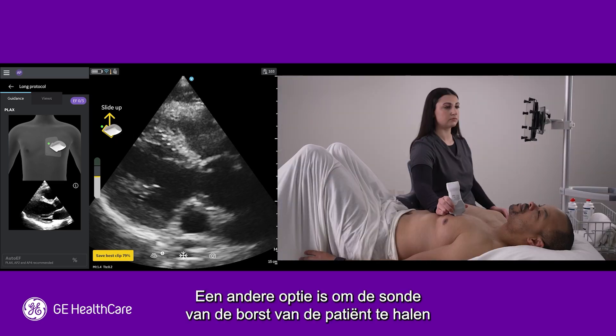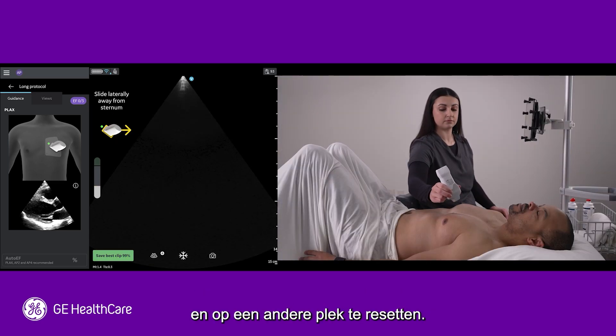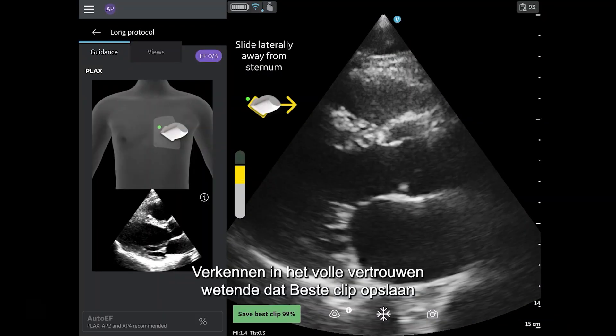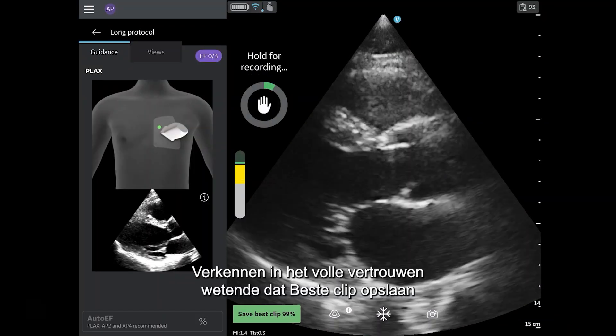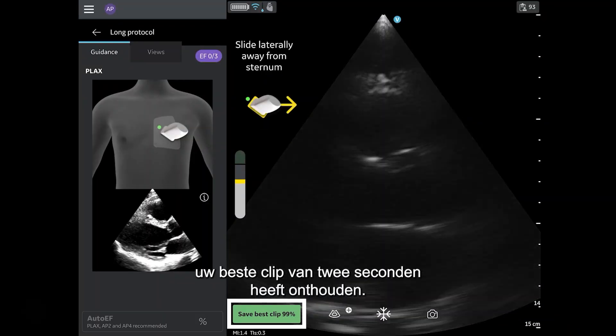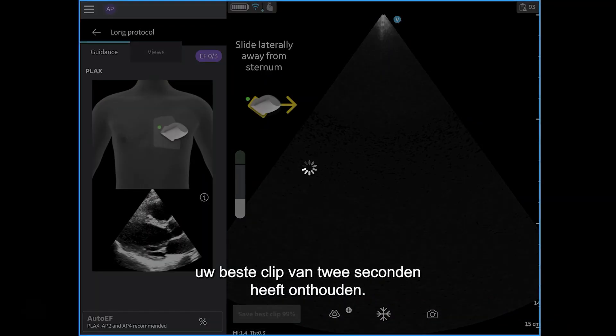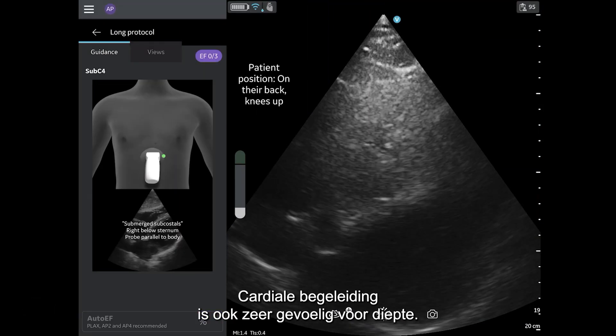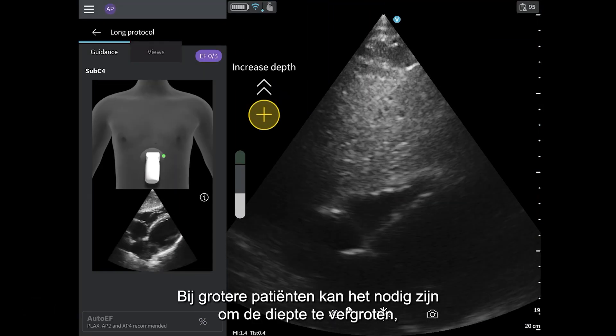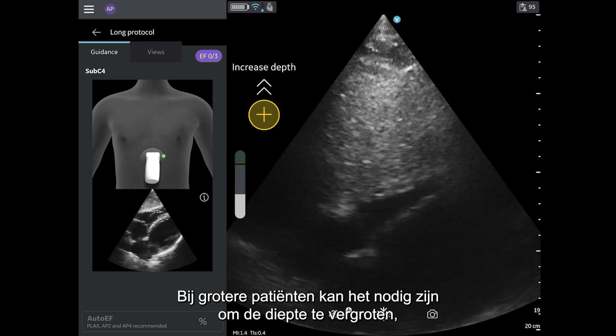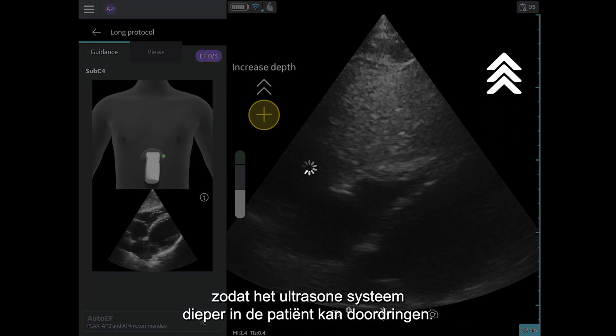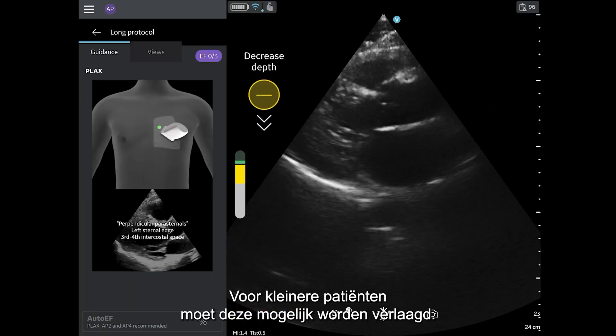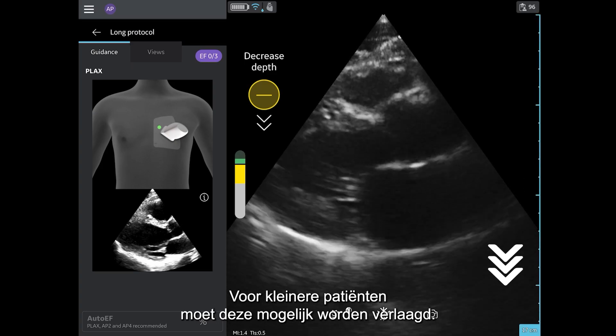Another option is to take the probe off the patient's chest and reset in a different spot. You can explore with confidence knowing that Save Best Clip has remembered your best two-second clip. Cardiac guidance is also very sensitive to depth. For larger patients, depth may need to be increased so the ultrasound can travel deeper into the patient. For smaller patients, it may need to be decreased.